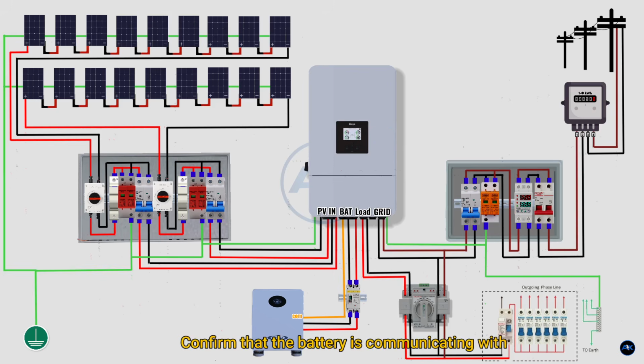Confirm that the battery is communicating with the inverter via the BMS interface and that charge parameters match the manufacturer's recommended values. With the system fully powered, we've successfully completed the commissioning phase. The next step is to configure operational settings and verify real-time performance using the DEYE monitoring platform.